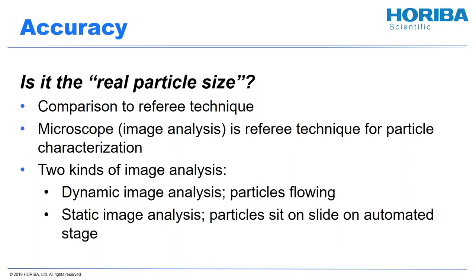On accuracy: is it the real particle size? That would be comparison to a referee technique. If you use a microscope and look at the particles, that's a very well-understood referee technique. For larger particles you can use a classical light microscope; you may need an electron microscope for smaller particles. One thing to watch out for is that you're measuring slightly different things with the two techniques, and particles are sometimes in different states. There are lots of different ways to define particle size under a microscope, so you would just pick one and say it's in the neighborhood of what we see with laser diffraction.